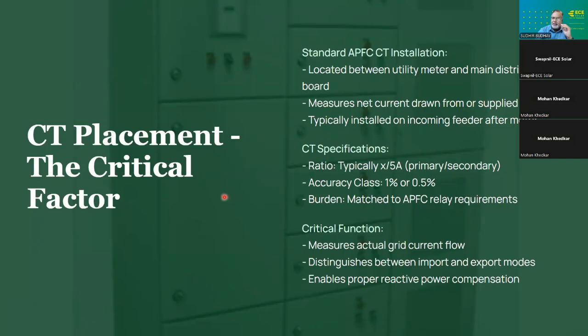They are generally located between the utility meter and the distribution board, so that they measure the entire current drawn. The ratios will be X by 5 depending on the whole current. You can design this ratio with accuracy class 1% or even better, 0.5. VA burden we can calculate. It measures the actual grid flow current and the import-export parameters also.